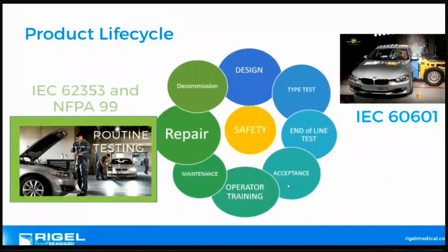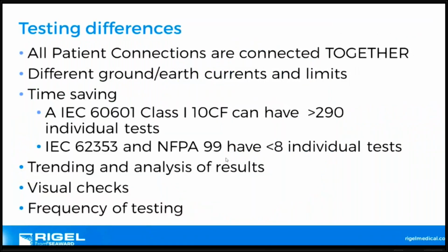There is some crossover in the line testing. You can do 62353 acceptance testing, but typically people would do 60601 for end of line and acceptance testing. What are the main differences? All patient connections are shorted together with NFPA 99 and 62353. With 60601, we test them individually, especially CF. Different ground and earth currents and limits, which I've discussed.